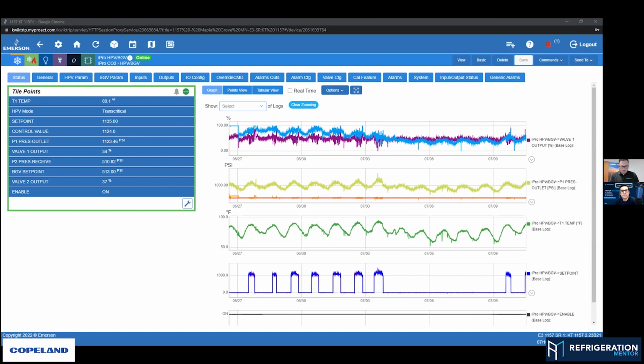So it's just pulled up here now. On this application, it also has the ability to do BACnet or Modbus communication, all out of the one controller. That's been really good for us, because previous models of case controllers had different valve types, which meant a different model, and different communication types, which meant yet another model. The product management team really did a good job getting it all into one part number. Emerson, or Copeland, is so big, with so many different control lines globally, so it's nice that you're taking the functionality from a lot of different product lines and making it one part number.